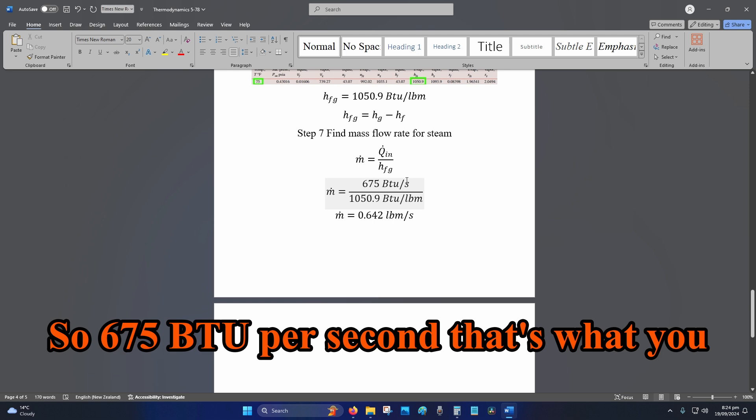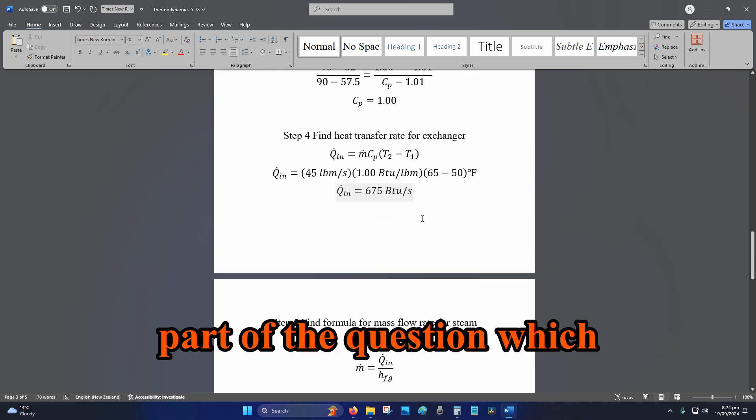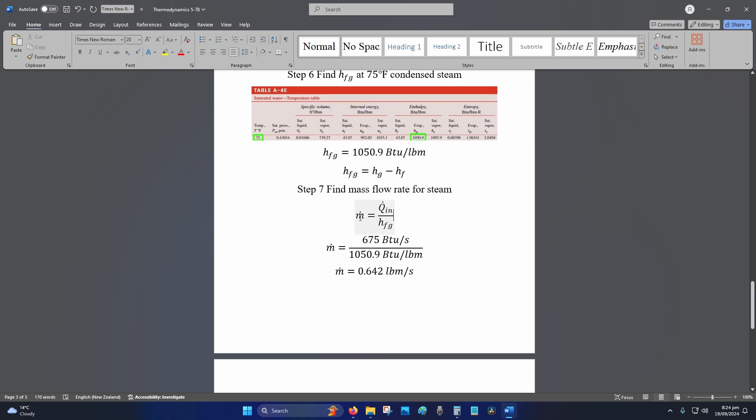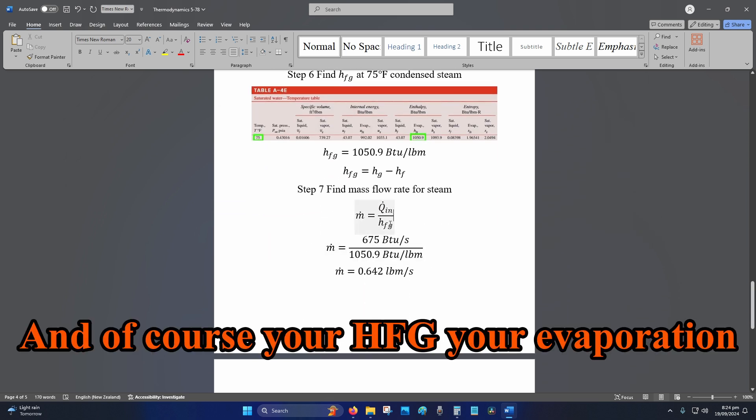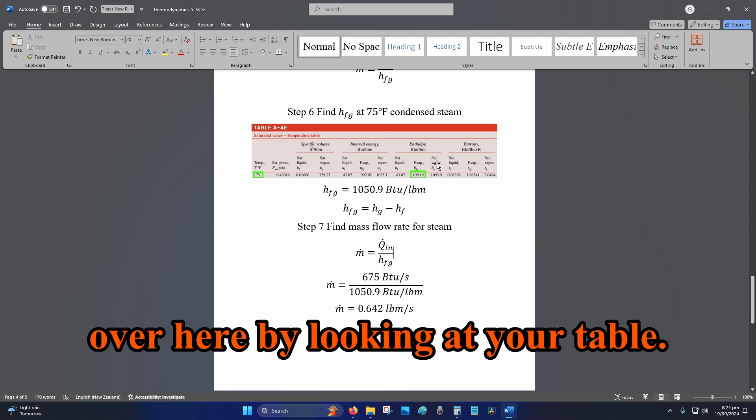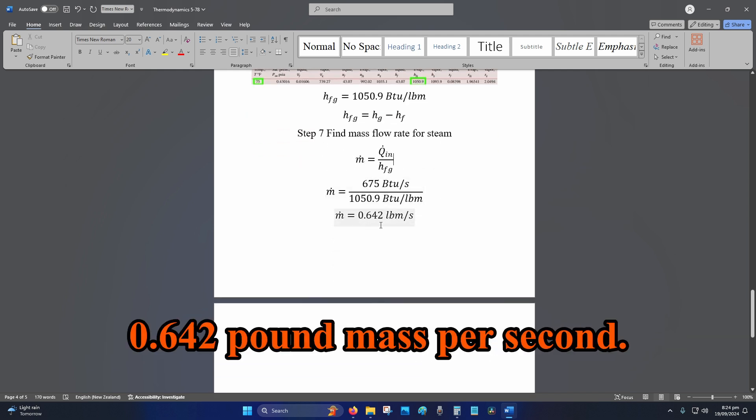So 675 BTU per second, that's what you figured out for the first part of the question, which is step four. And of course, your HFG, your evaporation enthalpy, is what you just worked out at step six, right over here, by looking at your table. So that will give you 0.642 pound mass per second.